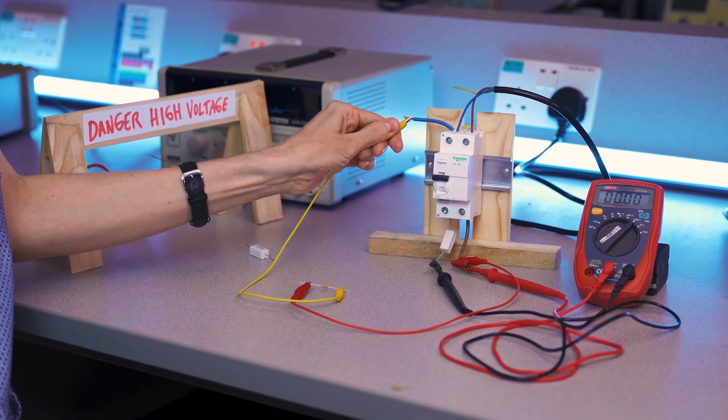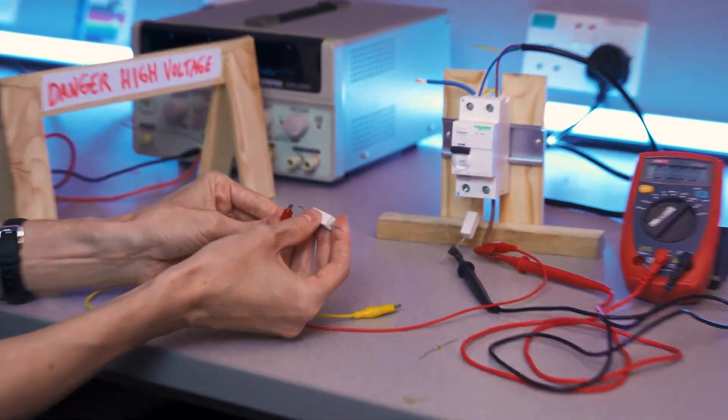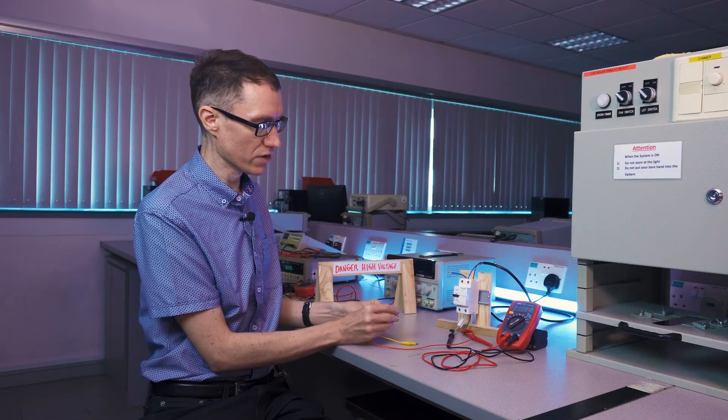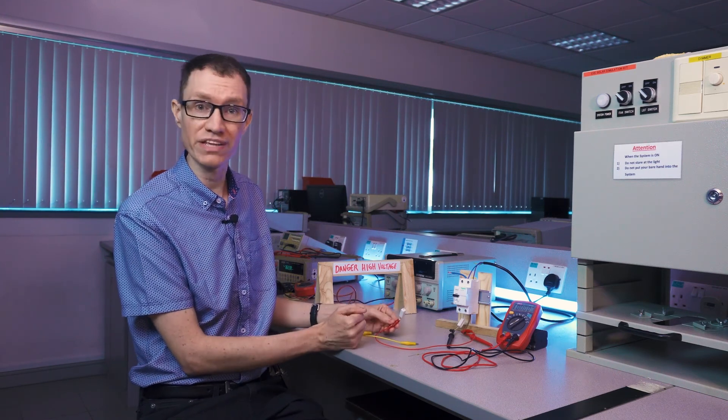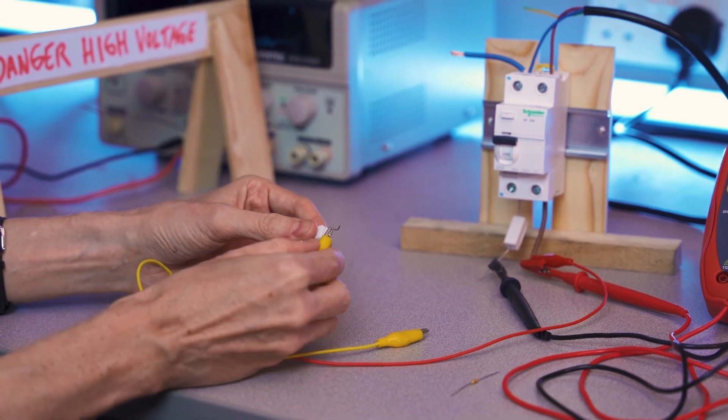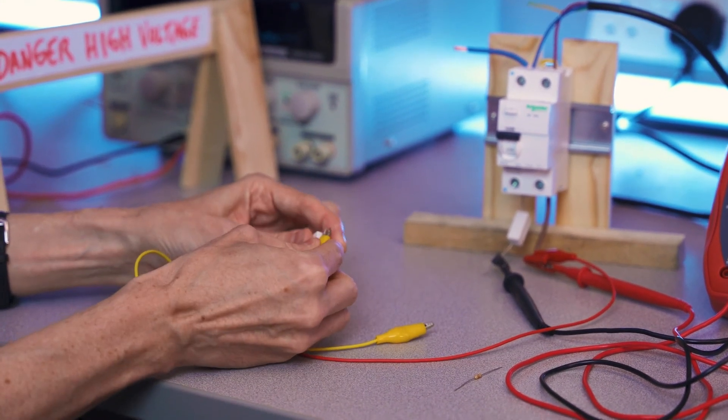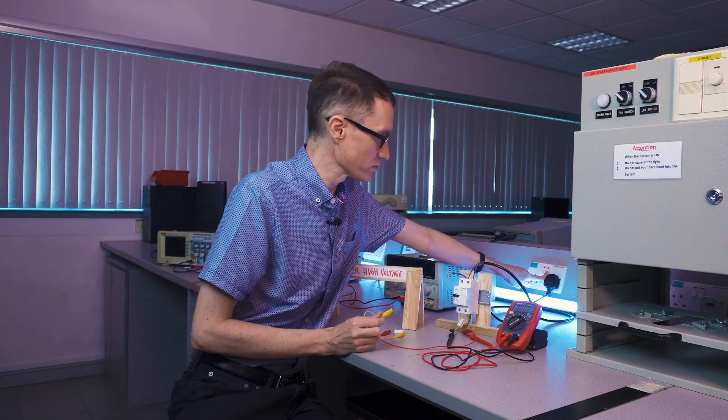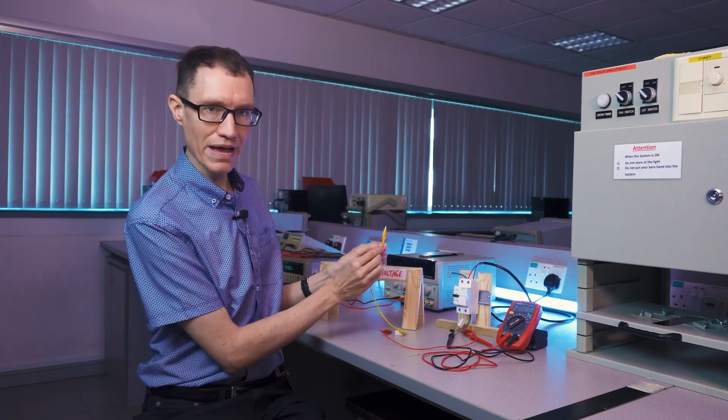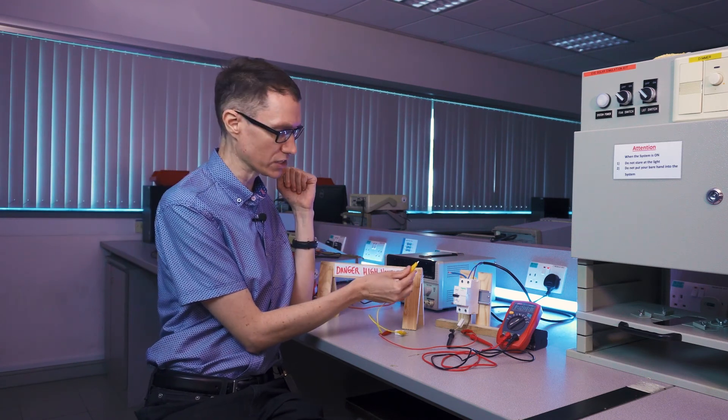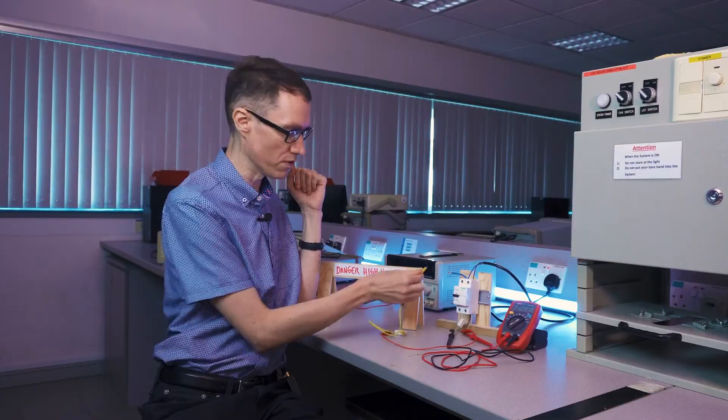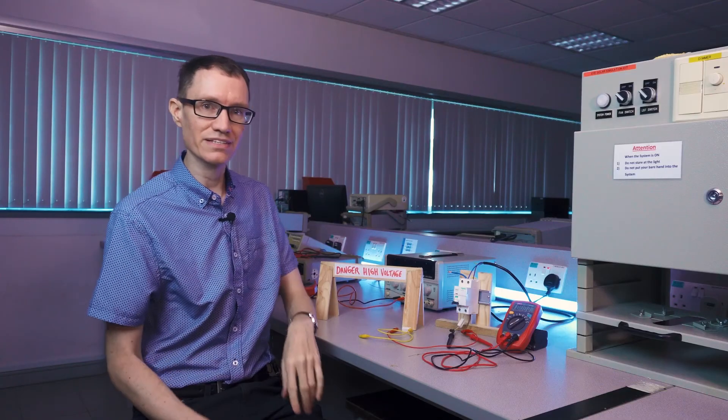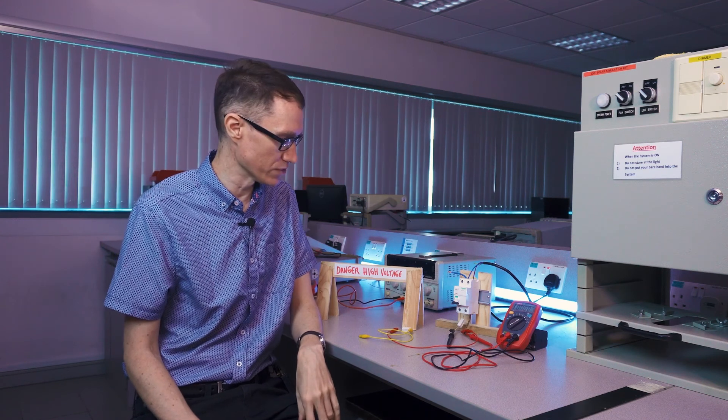I'll be replacing the 47 kiloohm resistor with a 10 kiloohm resistor, and we already know that a 10 kiloohm resistor should draw 23 milliamps. That's enough to cause this circuit breaker to trip if it works like it's designed. I'm going to go ahead and turn it back on now without the resistor in the loop. We can imagine somebody getting shocked as I make this final connection, which should cause 23 milliamps to flow through the fault. We can see that the circuit breaker works exactly as it was designed to.